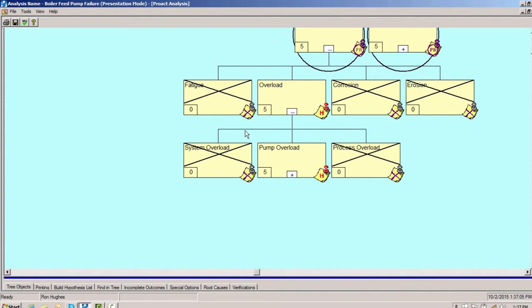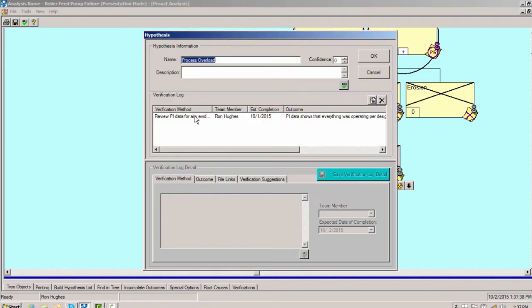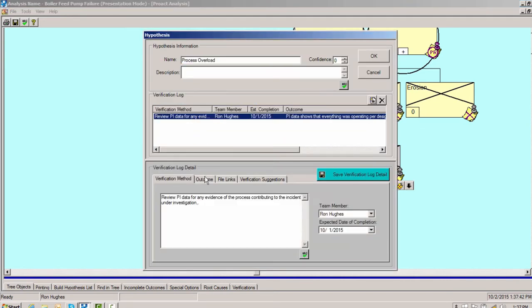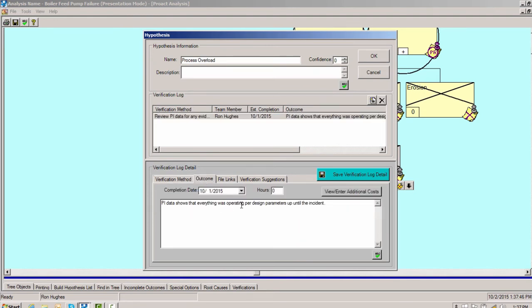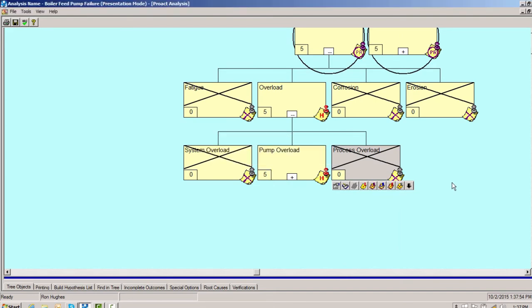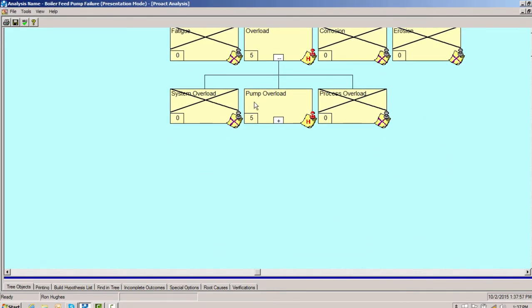So how can we have overload? It's either overloaded by the system, by the pump itself, or by the process. Overloaded by the system could mean cold springing in piping causing the pump casing to see unexpected loads — we check for that and there is none. The process would be the fluid media. We review the PI data and find everything was operating per design parameters up until the moment of the incident. So the process could not have contributed to it, but the pump is definitely overloaded.